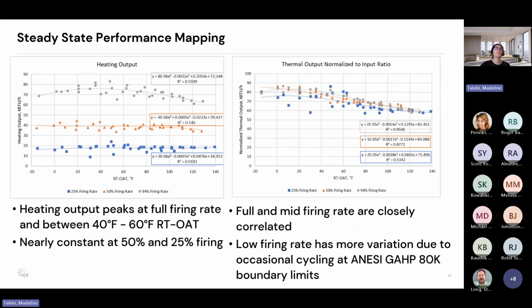And then looking at the heating output, we see it peak at full firing rate, and that happens between 40 degrees Fahrenheit and 60 degrees Fahrenheit. This is the normalizing unit that we're using for the x-axis: the return temperature minus the outdoor air temperature. It's nearly constant at 50% and 25% firing. We see very minimal, if not negligible, variation. So the heating output is going to, of course, vary depending on the firing rate.